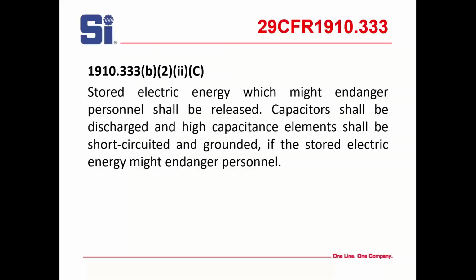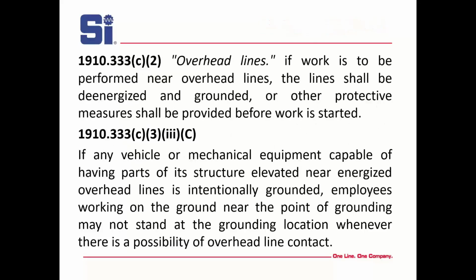So we look at 333, which is your general voltage, your medium voltage, and it says stored electric energy which might endanger personnel. Now we're talking capacitors, any type of capacitive equipment. That could be a long power line. So they have to be discharged and high capacitive elements short-circuited and grounded. Overhead lines: if work is to be performed near overhead lines, the line shall be de-energized and grounded.